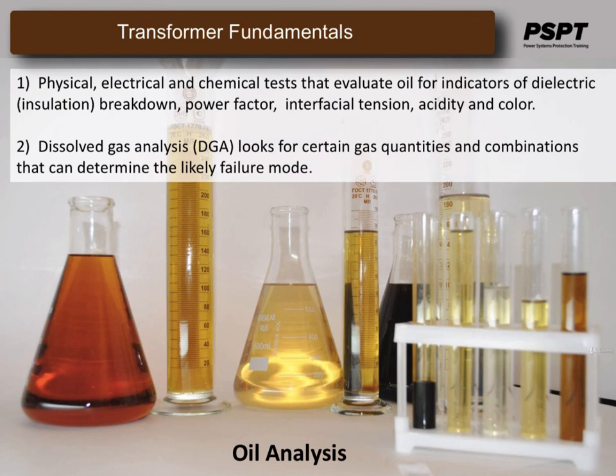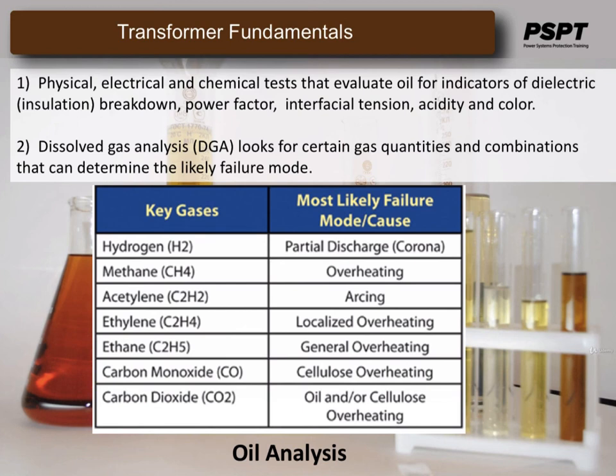The oil analysis is broken into two parts. Physical, electrical, and chemical tests can evaluate oil for indicators of dielectric insulation breakdown, power factor, interfacial tension, and acidity and color. Dissolved gas analysis, or DGA, looks for certain gas quantities and combinations that can determine the likely failure mode. Here are some of the gases that could be found dissolved in the transformer oil and their possible causes to be prevented.